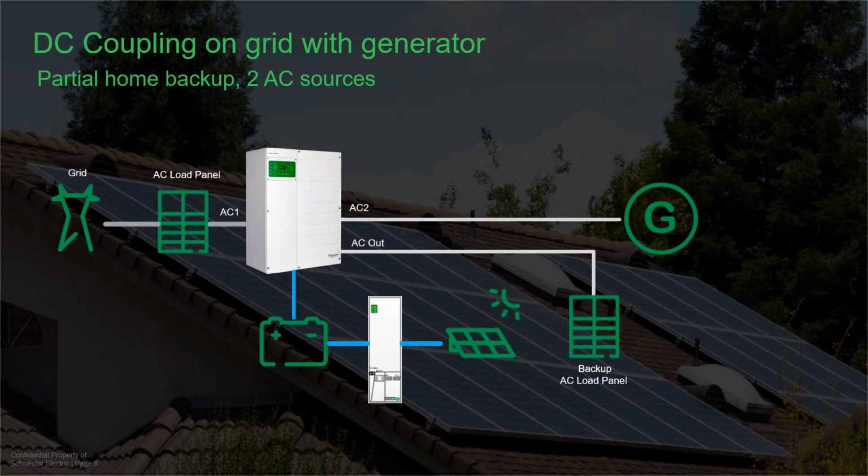If the battery ever gets low, the AGS will automatically start the generator to get the battery charged. You can program it to provide a partial charge, which allows PV to charge the battery fully. If the grid comes back while the generator is running, the generator will be stopped. Then the grid will be allowed to resume grid functionality. If the battery is still below the recharge setting, a charge will resume from the grid unless charging is blocked during peak hours. With notification of upcoming PSPS, you may wish to change how your system behaves. Thanks to Insight Cloud, these changes can be made remotely.